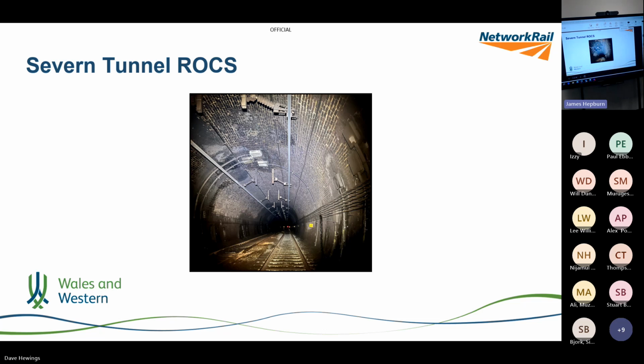There was also, because the system and the tunnel is carrying diesel traffic still, pollution on those polymeric insulators. They're very good, much better than porcelain, but they do have a drawback compared to porcelain because they don't have that nice ceramic shiny surface that you can clean. They are silicon rubber sheds, and when carbon and soot get into the surface, then they're extremely difficult to clean. And if a conducting material such as carbon covers the whole surface of the insulator, then you risk partial discharge and then eventually flashover and failure. And if you've got 1,400 insulators in there, there is then, of course, a maintenance liability with the potential for insulator failure.